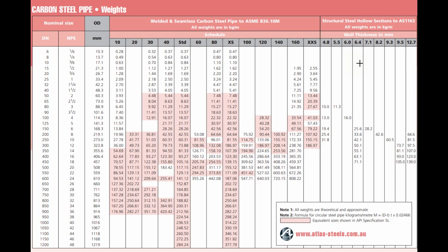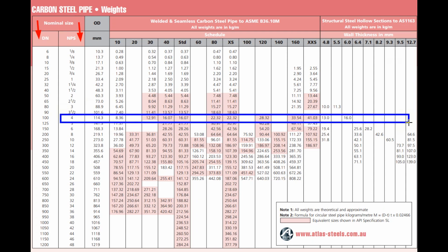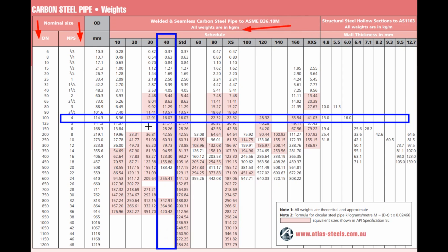This is a table for carbon steel pipe weight — you can also select the empty pipe weight from this table. The first column is for the DN system in millimeters and the second column is the NPS system in inches. Our pipe size is 4 inch, so we select the 4 inch row. The pipe schedule is 40, so we select the column for schedule 40. The unit of weight in this chart is kilogram per meter, meaning the weights given are for 1 meter length of pipe. For a 4 inch schedule 40 carbon steel pipe, the weight for 1 meter length is 16.07 kilograms.